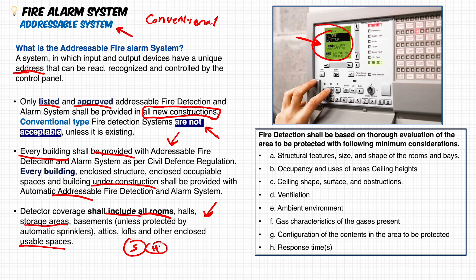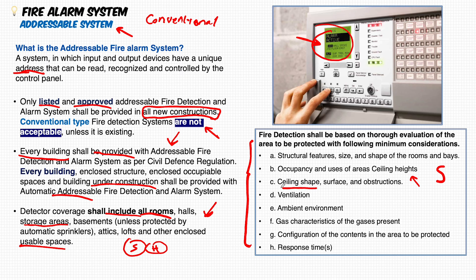We'll cover all related detector topics in coming lectures. Before proceeding, when designing a fire alarm system there are important considerations: structural features and room shape affect detector spacing distances; occupancy and use of areas; ceiling heights affect design; ceiling shapes; and ventilation — keeping detectors at some distance from ventilation or AC sources.